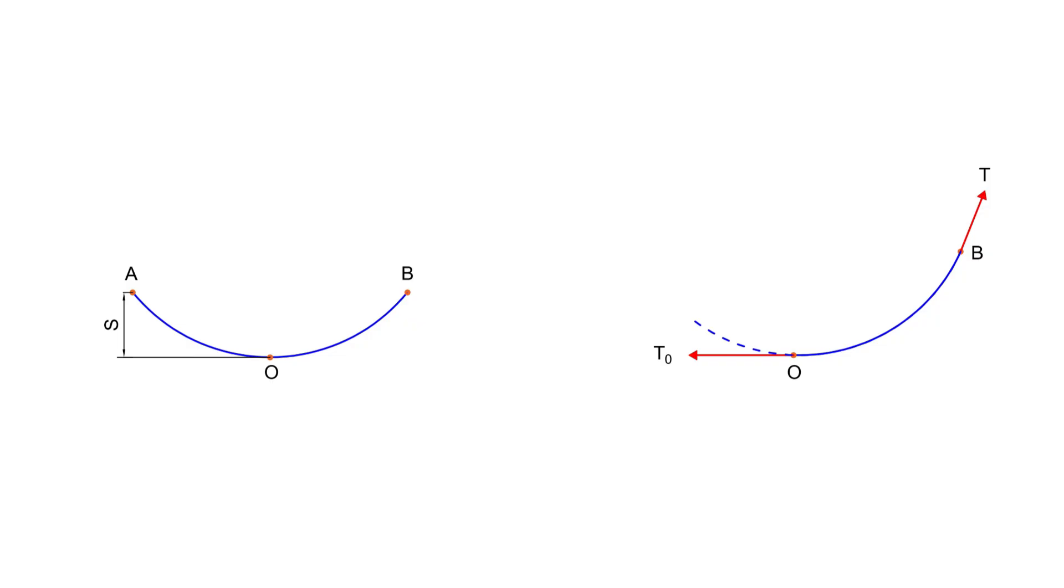The vertical dip from A or B down to O is called the sag S. A small sag keeps the wire safe, and too much sag requires taller poles, so we have to balance between conductor material cost and mechanical safety. Interestingly, the conductor curve actually forms a catenary shape, but when sag is very small compared to span it looks like a parabola.